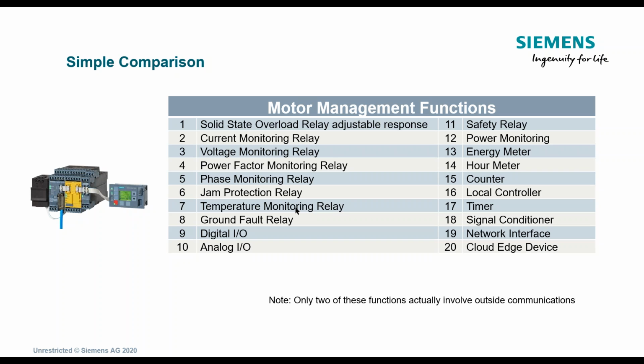Temperature monitoring. So another application is where Siemens, our SIMOCODE, looks at the entire process. Some motor management from other manufacturers is just looking at the overload, turning it on and off, counting maybe how many times it turns on and off, and that's about it, and maybe reporting the current and voltage. But what else we can do with the SIMOCODE is add on an RTD module and put RTDs up to 6 and measure temperature on gearboxes, pump housings, pillow block bearings, so the SIMOCODE becomes not just the motor management and not just a simple smart overload, but an entire process diagnostic tool.